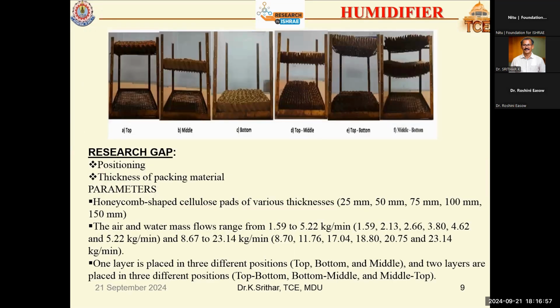So based on that, this is the position we have for the packing material. We have 3 layers of position arrangement for the packing material. This arrangement will be fixed inside the humidifier. In the first arrangement, we have the packing material placed only on top. In the second, the packing material is placed at the middle. The third one is the packing material fixed at the bottom, that is nearest to airflow. Top means nearest to water flow. The other fixations are top and middle, top and bottom, and top, middle, and bottom. So all the possibilities we have checked.